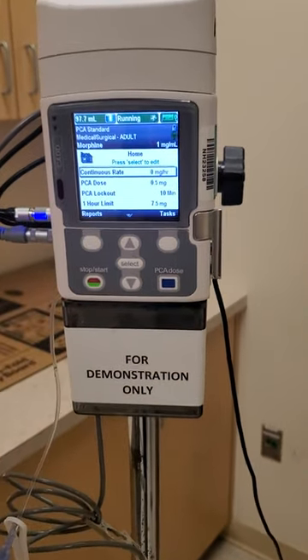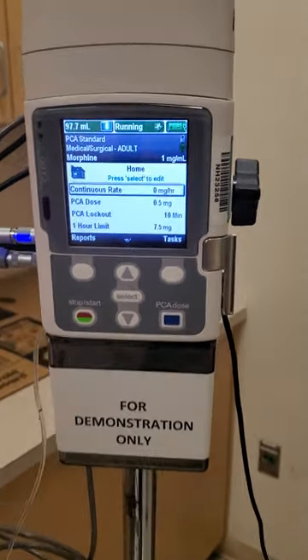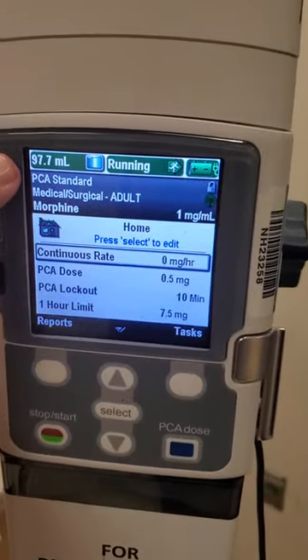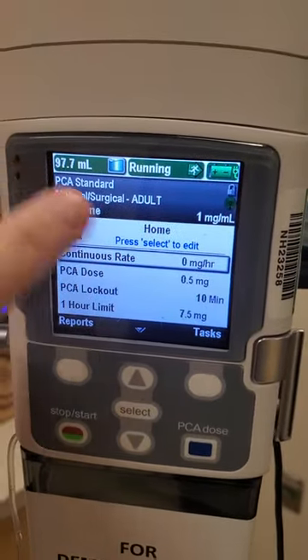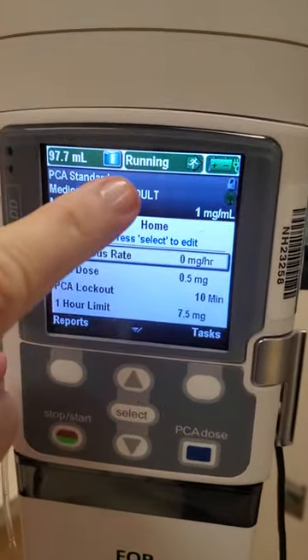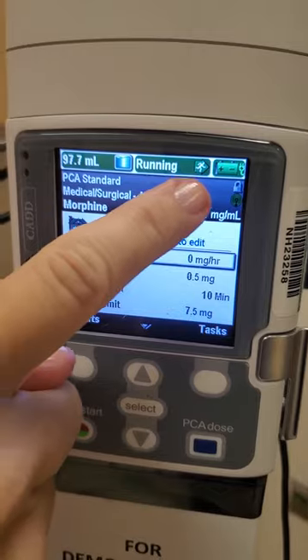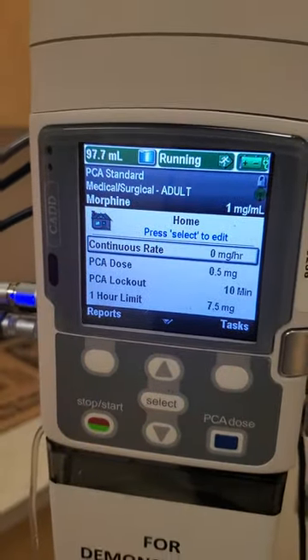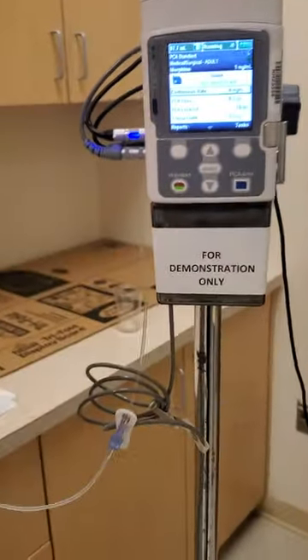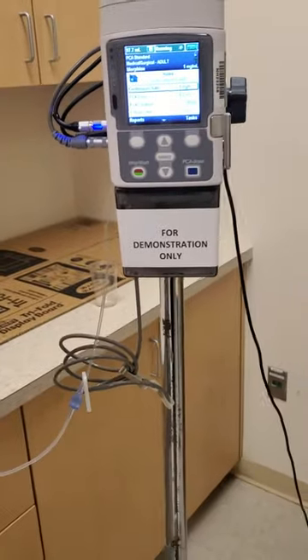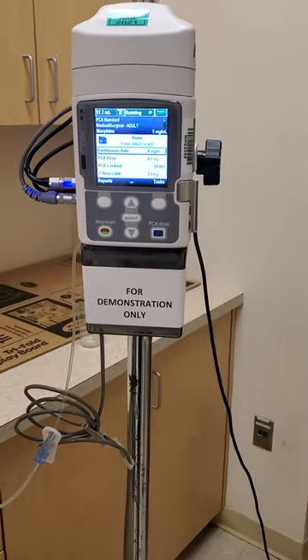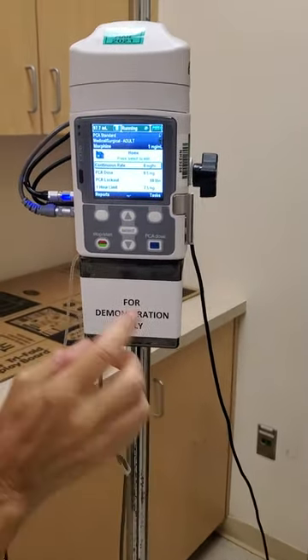I hit the start button and now you can see the reservoir volume, confirming it's running — you see the little figure in the arrow running and you can see your battery life. I have it plugged in, but it can also run on battery so you can unplug it if you need to move the patient around.